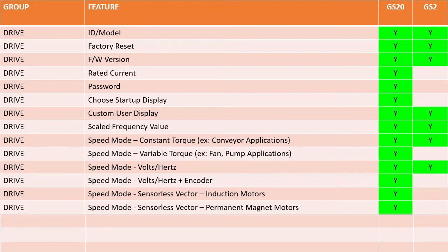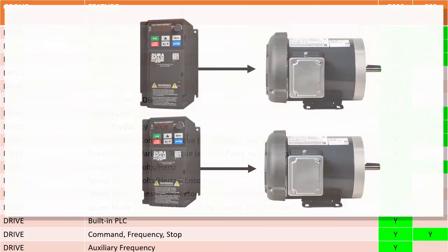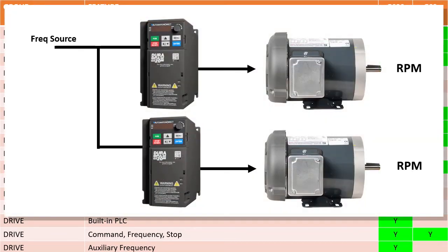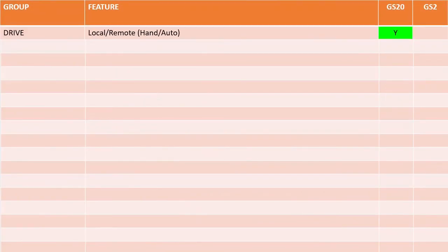The GS20 drives have a built-in PLC which you can program using the free GSLogic software and a USB cable to handle any extra functionality you want to add to the drive. Both drives have the usual frequency, command and stop methods, but the GS20 has a second or auxiliary frequency source that you can use to offset the drive frequency. For example, if you have two drives running off the same frequency source, you can use the auxiliary frequency source to add an offset to the second drive to tweak the second motor speed relative to the first. The GS20 gives you both local and remote operating configurations so you can have the drive operate one way when standing right in front of it and another way when remotely controlling it. The GS2 only has one operating mode.